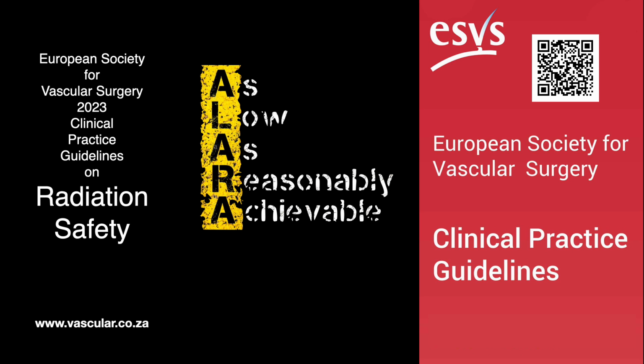Because when you select a smaller detector area, a smaller field of view, or FOV, the system's automatic brightness control, ABC, or automatic exposure control, AEC, automatically increases the radiation output, tube current or pulse width, to maintain the same brightness level on the monitor. So smaller area needs more juice to look as bright. Precisely. The dose increase is roughly inversely proportional to the square of the change in FOV diameter. So if you halve the FOV diameter, you roughly quadruple the radiation dose rate to that small area.